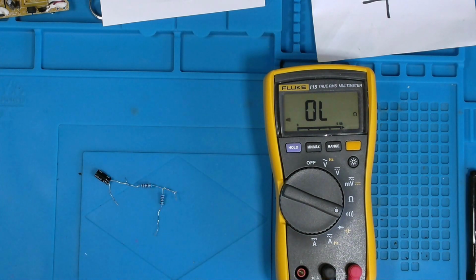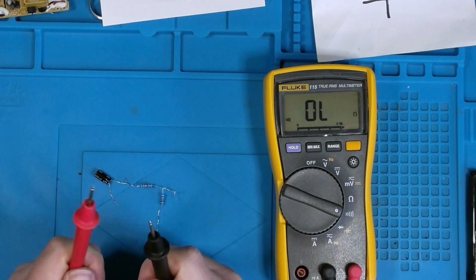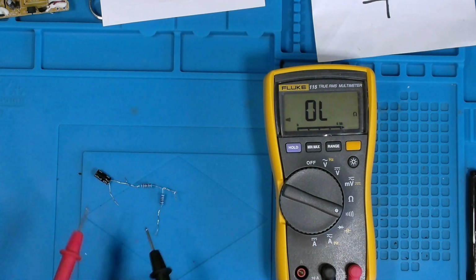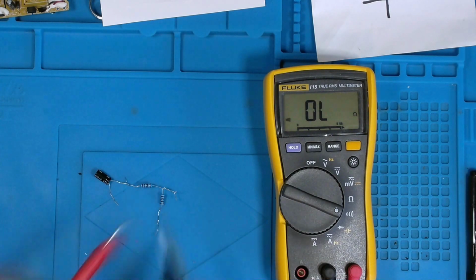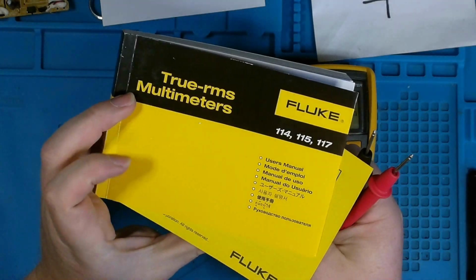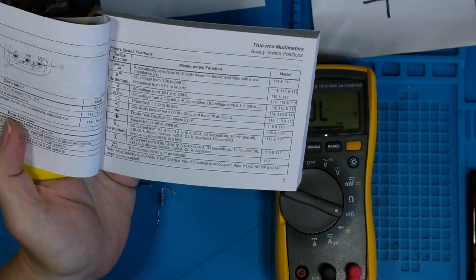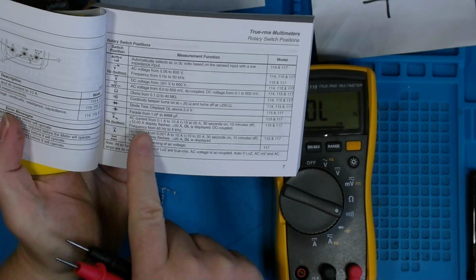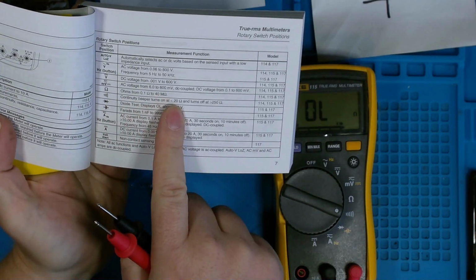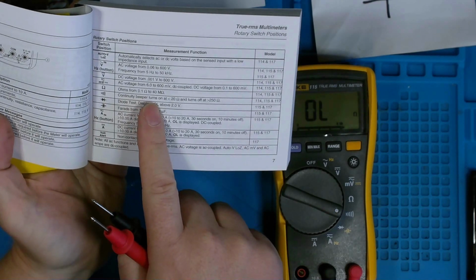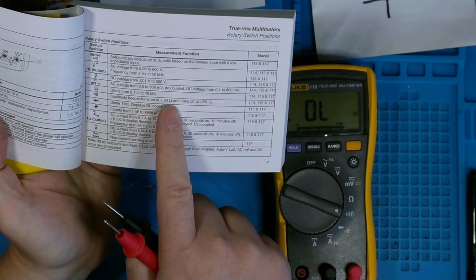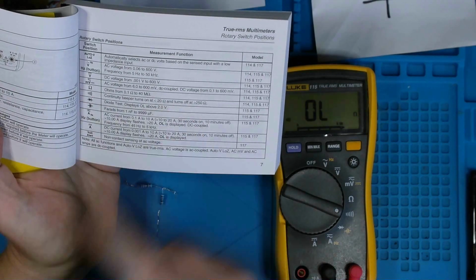Because you're using the internal battery voltage and the application of coupling your leads to the circuit to make this continuity measurement. It's also extremely wise to check your Fluke or whatever book came with your multimeter to see the ranges allowable to get that audible tone. We get a continual beep at less than 20 ohms, and it turns off at greater than 250 ohms.